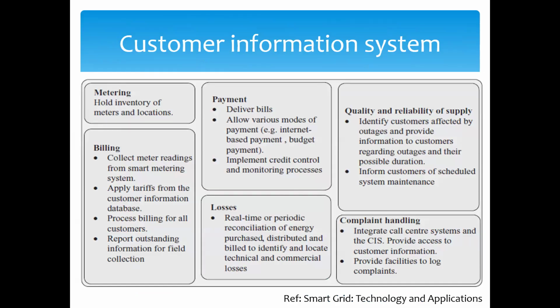Customer information system. What does it have inside the customer information system? Metering. Information about metering, billing, payment, losses, quality and reliability of supply, and complaint handling. Those pieces of information are inside a customer information system. Regarding metering, it holds an inventory of meters and locations. So when there's an issue in the field, we can easily locate it. Every customer premises has a GPS location, so once a person makes a complaint, it's easy to go and find that customer in the field.